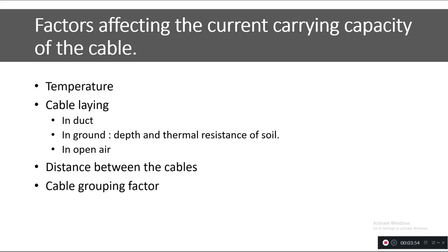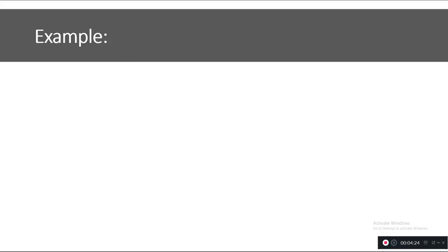Next is the cable grouping factor. If the number of cable runs is more, you need to lay the cables in a particular manner — typically in a cable tray. This grouping of cables affects the current carrying capacity. You need to understand and consider this factor when calculating the current carrying capacity.